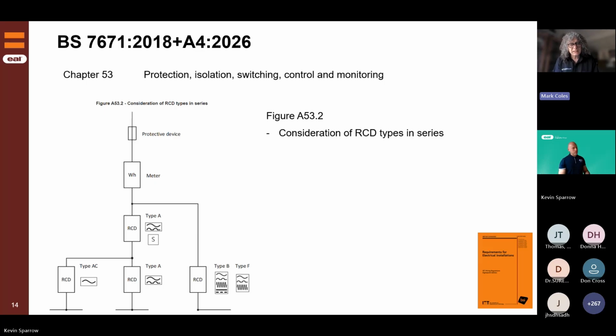What this shows you is that you've got to be careful about where you put the particular type of devices. Now, the AC RCD, for example, has been outlawed in countries like Germany, where it was the 1980s, and they just don't use them because they're suitable only for resistive loads like old-style showers, equipment that doesn't have any electronics in it, because electronics can impose DC waveforms. Conventionally DC doesn't have a waveform, but if it's pulsing, you could look at it like that: it's DC, it's DC, it's DC. Now certain devices like this type AC device don't cope with that very well.